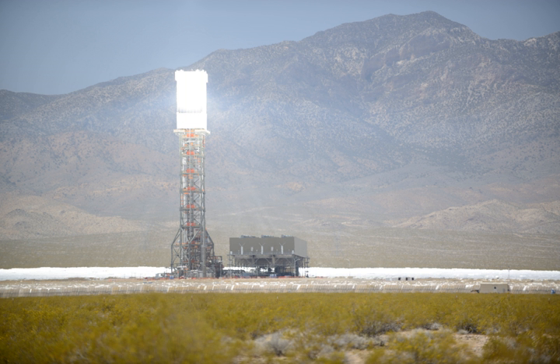During the first six months of operations, a total of 321 birds were killed. After altering the standby procedure to focus no more than four heliostats on any one point, there have been no further bird fatalities. The Ivanpah solar power facility is classified as a greenhouse gas emitter by the state of California because it has to burn fossil fuel for several hours each morning so that it can quickly reach its operating temperature.